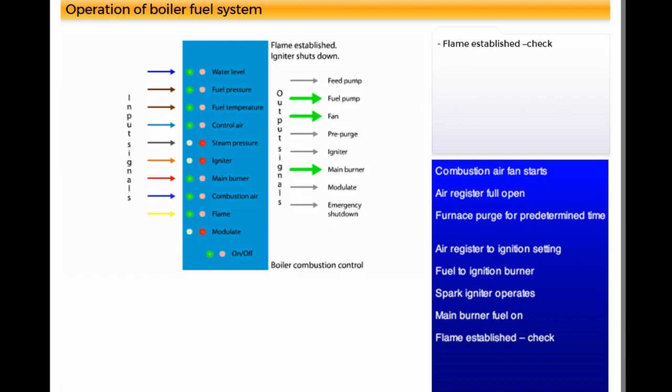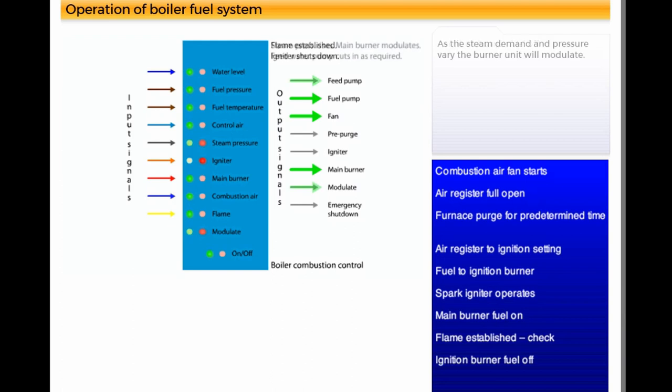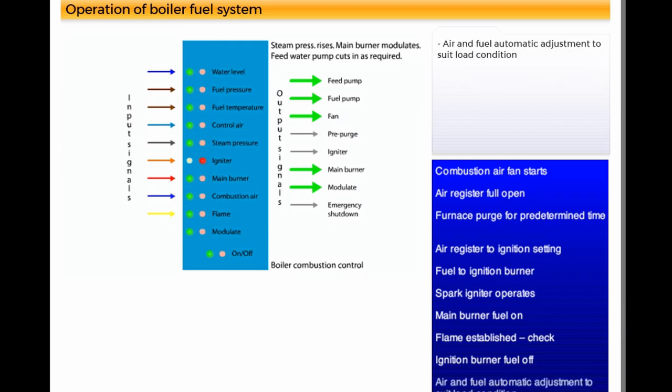Flame established check. Ignition burner fuel off. As the steam demand and pressure vary, the burner unit will modulate. Air and fuel automatic adjustment to suit load condition.